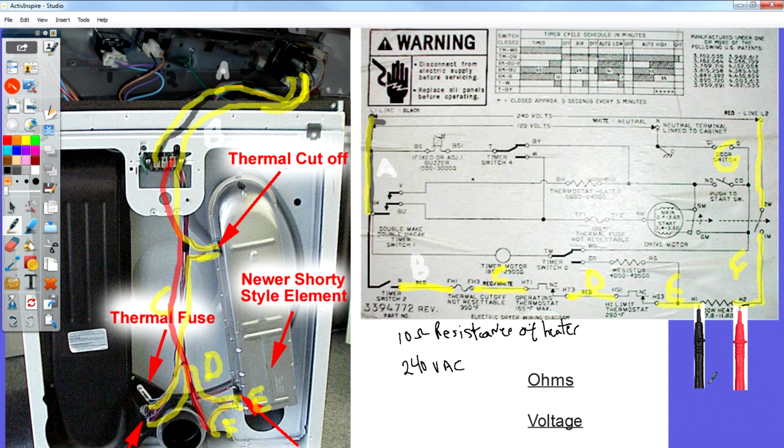Wait, hold on. This is based on the meter leads in the schematic. My meter leads where they are. Yeah. I'm getting a reading of 240 volts AC. That's the same as putting the meter leads here and here. Okay? Am I testing the heating element? Yes. No. You're testing this. You're testing the line. Okay? I'm testing the circuit. Carl, you're right about the line.